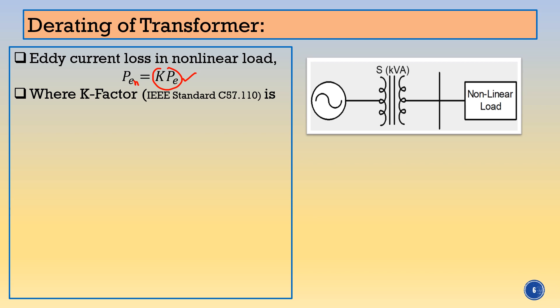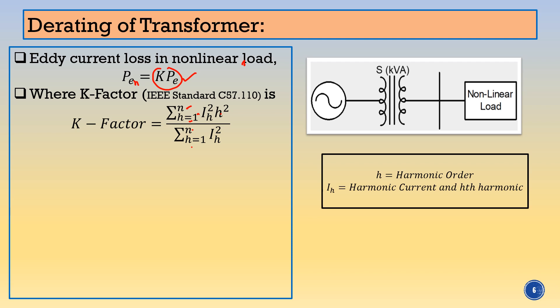According to IEEE standard C57.110, the K factor can be calculated as: K = [Σ(IH² × H²)] / [Σ(IH²)], where the harmonics H varies from 1 to N. Here H stands for harmonic order and IH stands for harmonic current at the H-th harmonic.